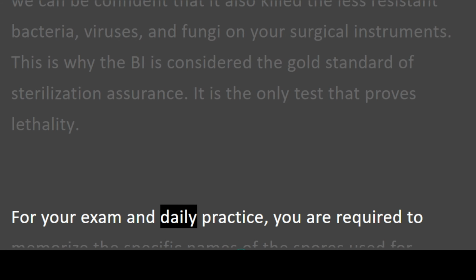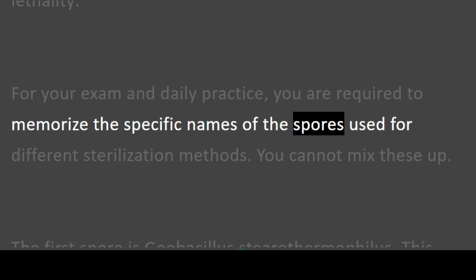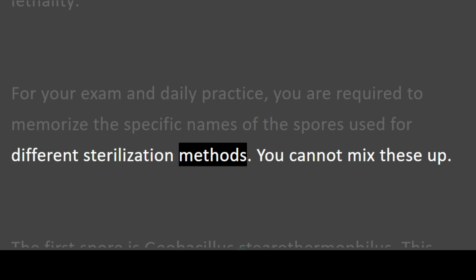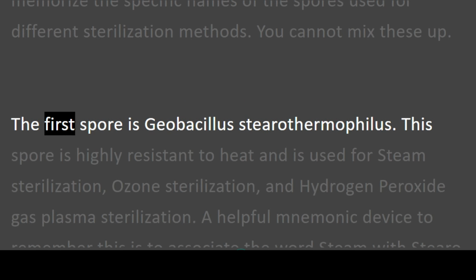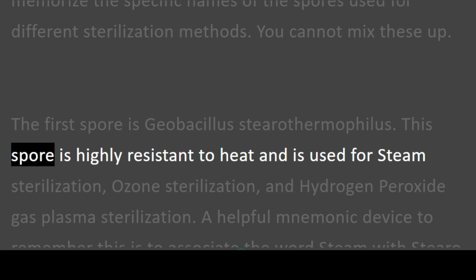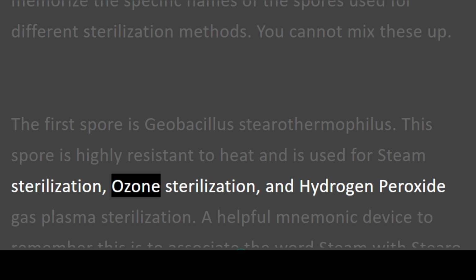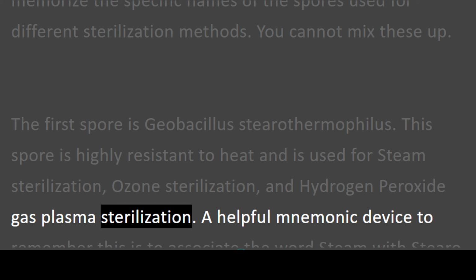For your exam and daily practice, you are required to memorize the specific names of the spores used for different sterilization methods. You cannot mix these up. The first spore is Geobacillus stearothermophilus. This spore is highly resistant to heat and is used for steam sterilization, ozone sterilization, and hydrogen peroxide gas plasma sterilization.